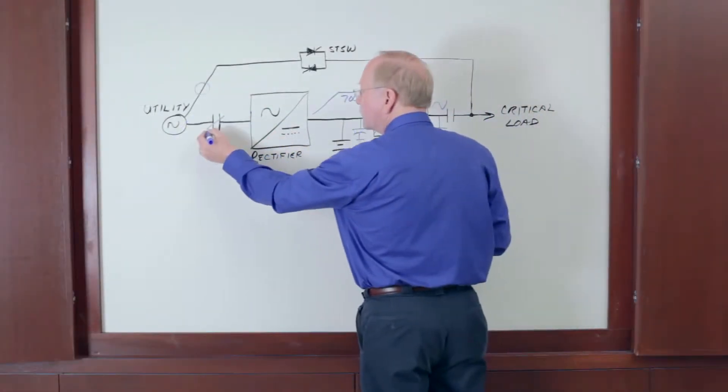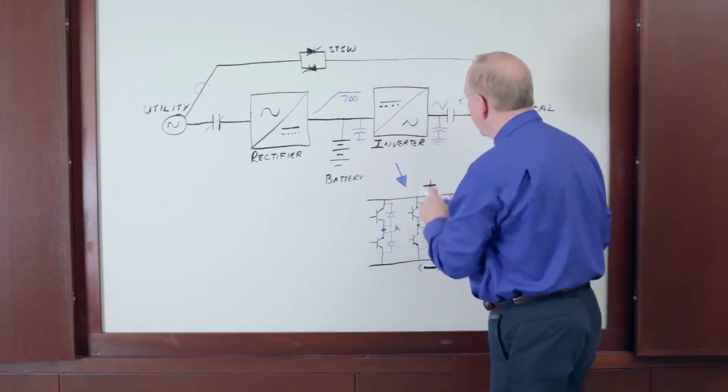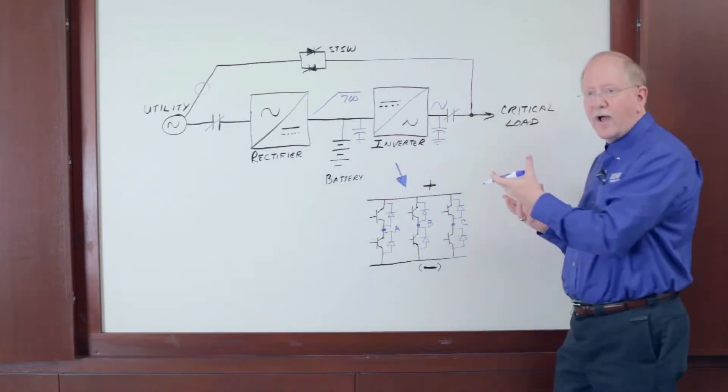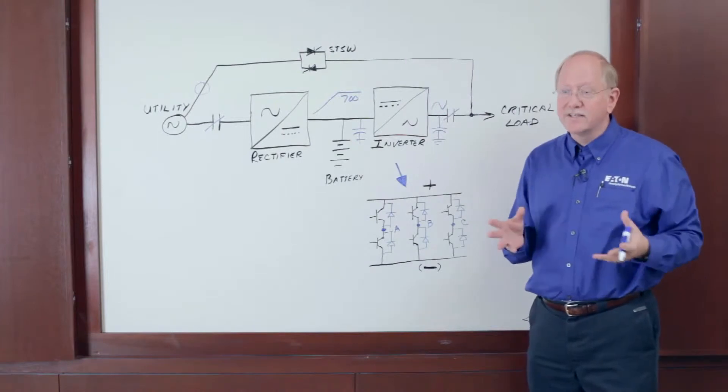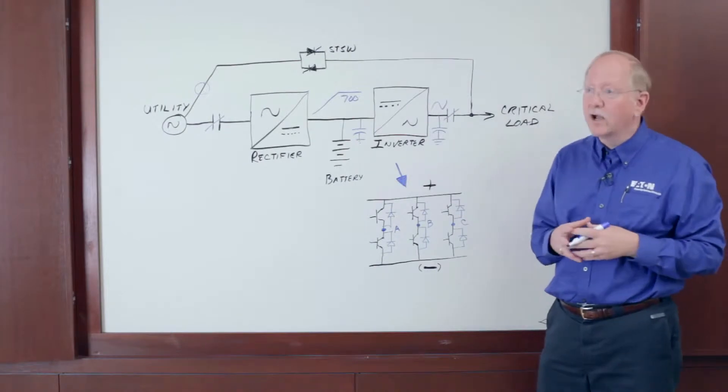So close the input contactor, ramp the rectifier for 30 seconds, turn on the inverter, synchronize the inverter, finally close the output contactor, and you have an output from the UPS. The process takes two to three minutes. It's much too long. So how does it work in a modern eco mode?